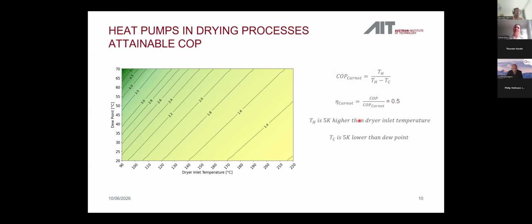And then, of course, you need both temperatures, the high temperature and the cold temperature. The sink side temperature depends on the needed dryer inlet temperature, and for sufficient heat exchange, we added 5 degrees Celsius for the heat exchanger. And we did the same on the cold side, on the source side of the heat pump, where we said that the dew point is decisive for the temperature there. So we assume that the cold temperature is 5 Kelvin lower than the dew point. And then you can create such a map where, using your parameters for the drying process, you can have a first estimation of the COP that you would achieve when adding a heat pump into your drying process.